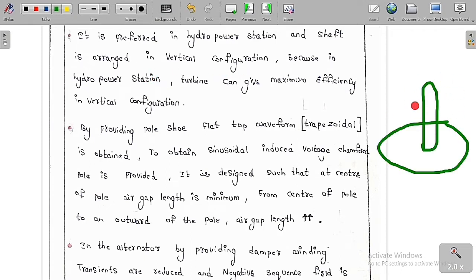So this is what I mean, which is called the vertical configuration. The shaft will be vertical and the stator is going to be kept on the ground. You can see they keep it on the ground like this, stationary in horizontal fashion, and this is called the rotor. The shaft is kept in the vertical direction. Water is going to flow in here and rotate this turbine, so therefore we produce electrical energy. If you keep the shaft in the vertical position, there will be maximum efficiency in these turbo alternators. So it is preferred in the hydropower station and the shaft is always arranged in the vertical configuration, because in a hydropower station the turbine can give maximum efficiency only in the vertical configuration. That is the reason we keep the shaft in the vertical configuration, and this is the stator, in a horizontal fashion.